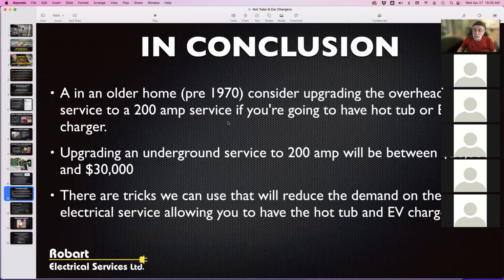Okay, let's talk about reducing the demand for the hot tub and so forth. There's a thing called a load miser, to reduce the amount of current you're drawing on the main service. Let me give you an example. Let's say you call Robart Electric and we do a load calculation for $150, and it comes out that you've got 115 amp demand on the 100 amp electrical service.